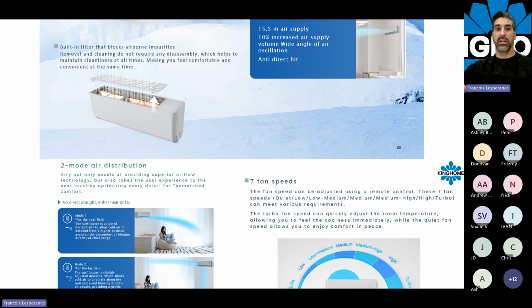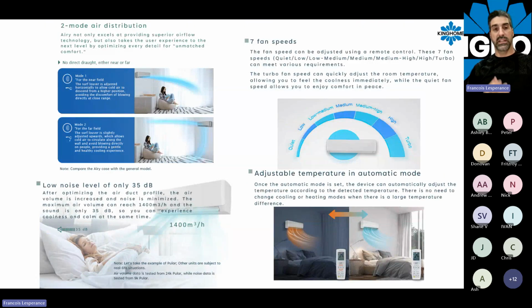This will give us the ability to avoid direct air on the skin or on the people in that room. So, for example, you can select one mode that pushes the air across the ceiling, just making it like the farthest you can push the air before it drops down. Or another option is to push a certain amount of air across the ceiling and another portion directly on the floor. So that will have some effect to create a bubble inside that room. So the temperature will drop very quickly, and you still avoid having direct air on the skin.